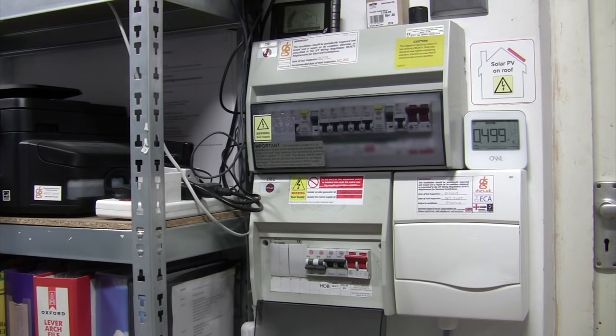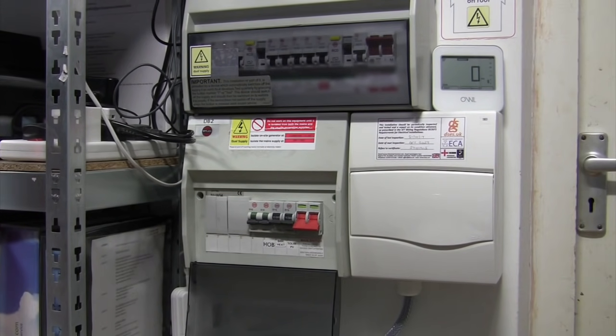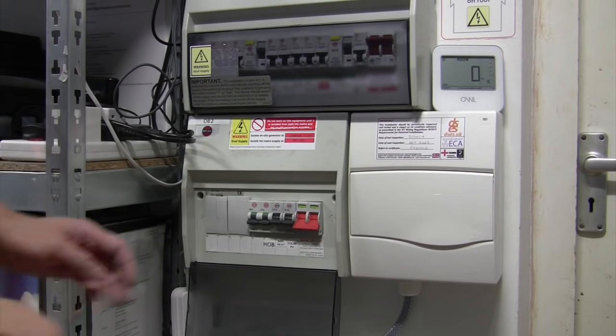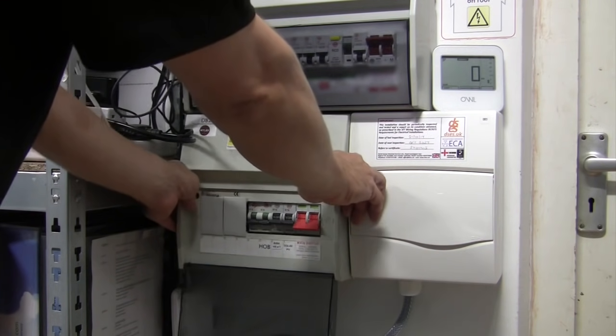As mentioned earlier, I'm on a 60 amp PME feed, so DB3 runs my 8.5 kilowatt electric shower via a contactor to ensure the car charge point won't operate if the shower is in use. That's just to keep my maximum demand down and prevent my puny 60 amp fuse from vaporising in a cloud of fishy smelling smoke. This SPD probably isn't type tested for my Elex board, but to hell with it, it's my installation and I'm prepared to live with the risk.